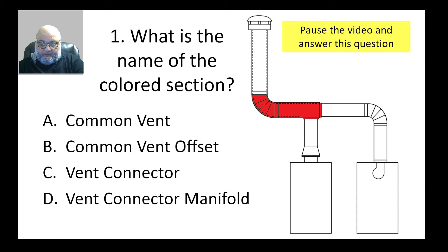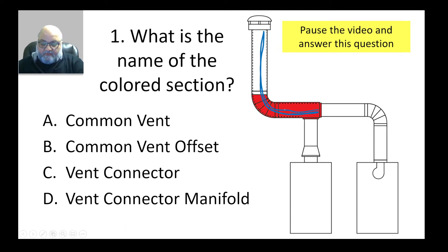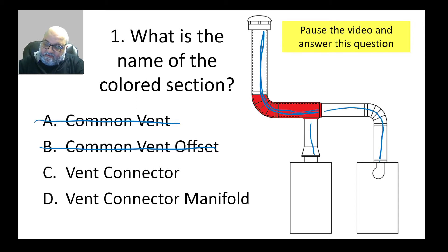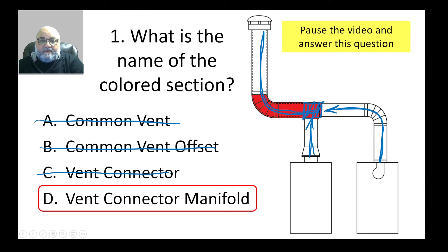The correct answer is not 'common vent' because the red part is just a portion of the common vent — the whole section together is the common vent. It's definitely not a common vent offset because I don't see two elbows, which define a common vent offset. And it's absolutely not a vent connector — those are the vent connectors bringing the vent gas streams and combining them at that junction.